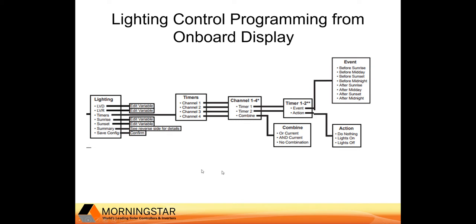Let's take a closer look at the lighting variables available for programming. LVD and LVR are the settings for the battery voltage value you would want to set to turn the load off, or turn the load back on again when the battery begins to recharge. Timers are used for setting when to turn the lights on and off and for how long. Sunrise is the setting for what percentage of array voltage triggers the sunrise flag. Sunrise and sunset typically do not need to be adjusted unless there is an issue with ambient lighting or very low solar resource. The summary gives a basic visual of how the lighting is set, and save config is critical and is used to save the programming you have set up.